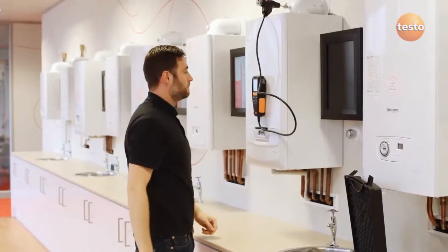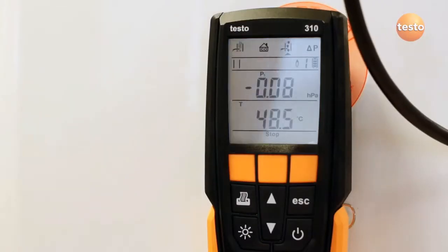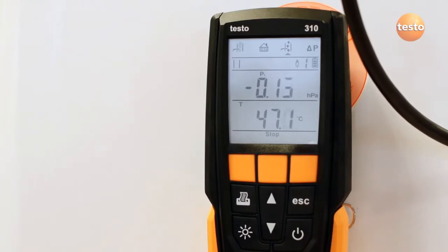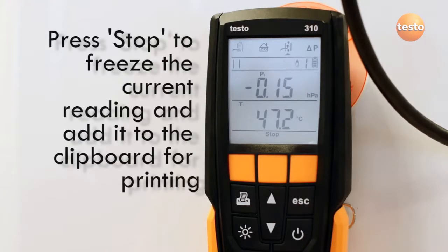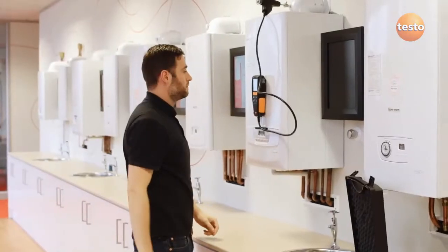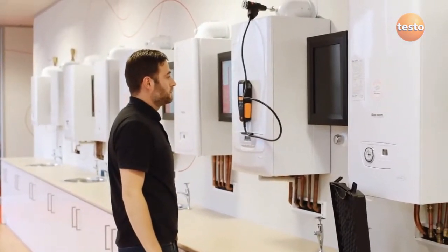The 310 immediately displays the small pressure caused by the flue draft. When the reading is stable, press stop, which freezes the current measurement and puts it in the clipboard for printing later.